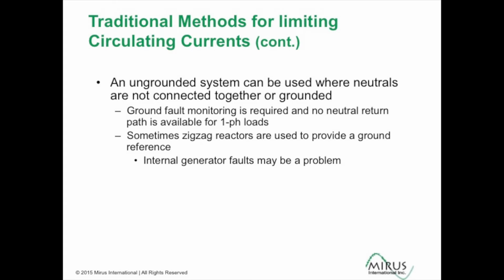And of course, we can apply an ungrounded system where we don't ground the neutrals. Doing that, codes require that we be monitoring for ground fault, and we indicate that because our protection is not going to interrupt a ground fault now. Sometimes zigzag reactors are used in this type of situation to create the ground reference, but those don't always provide fault paths for internal faults in generators.